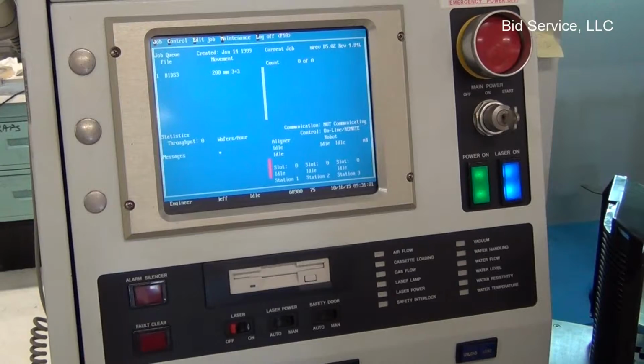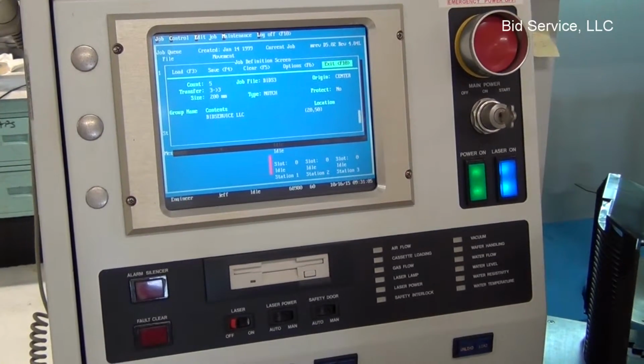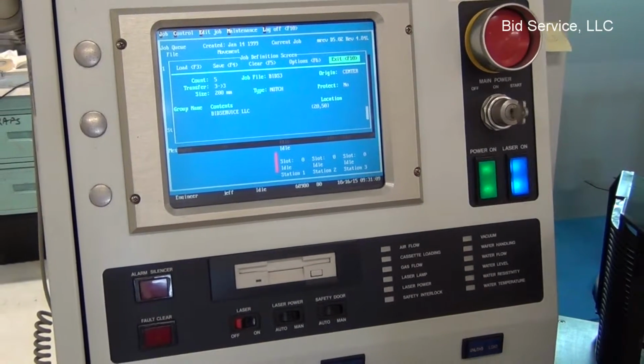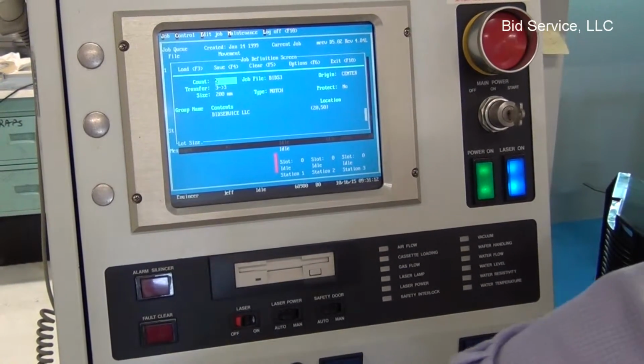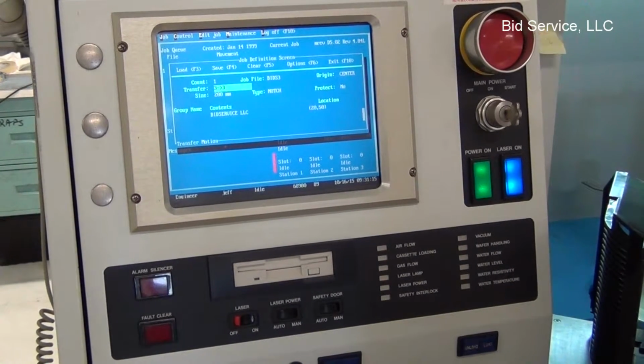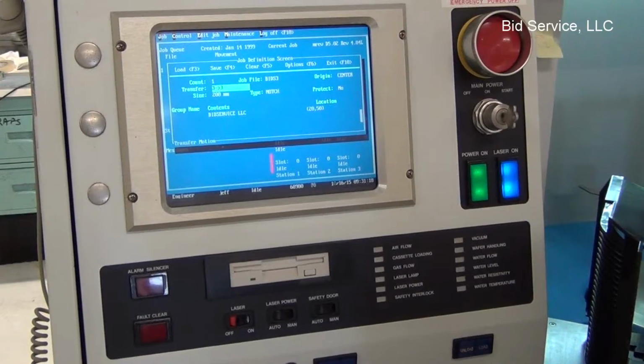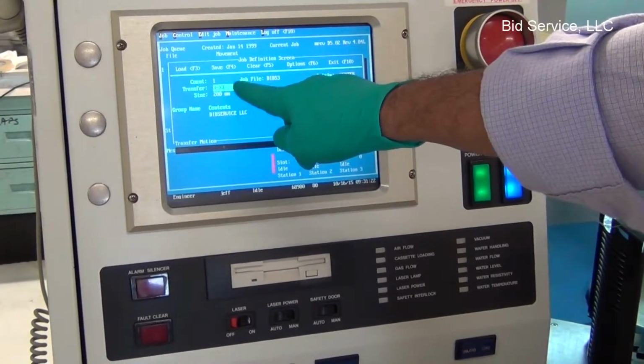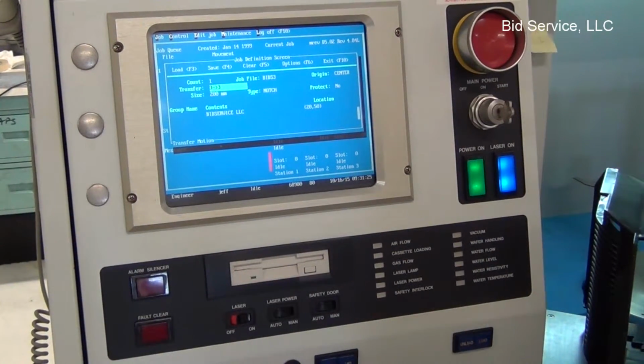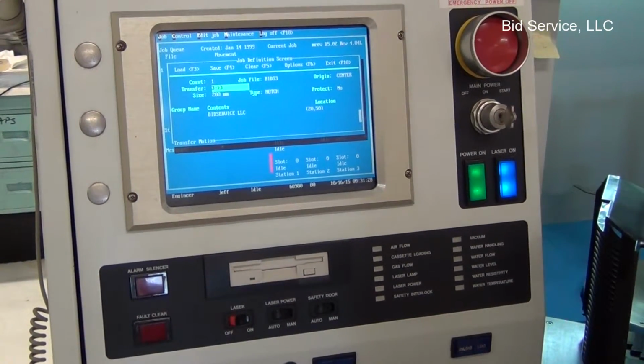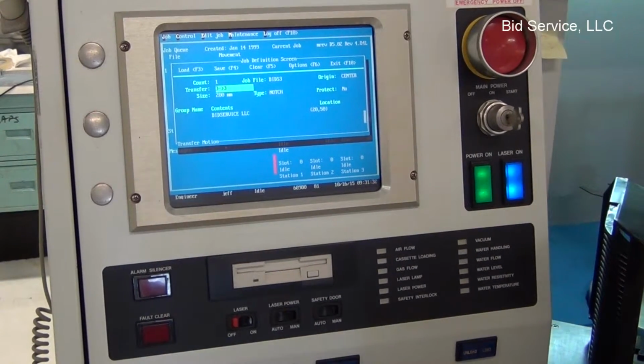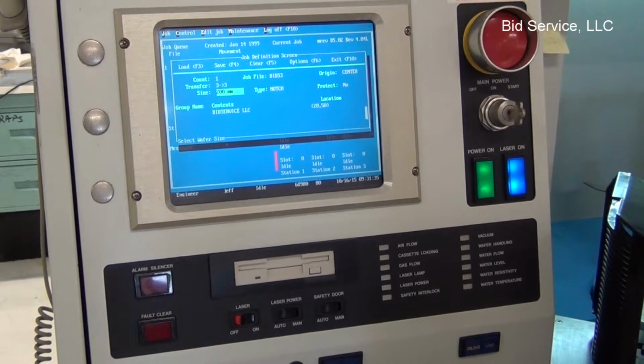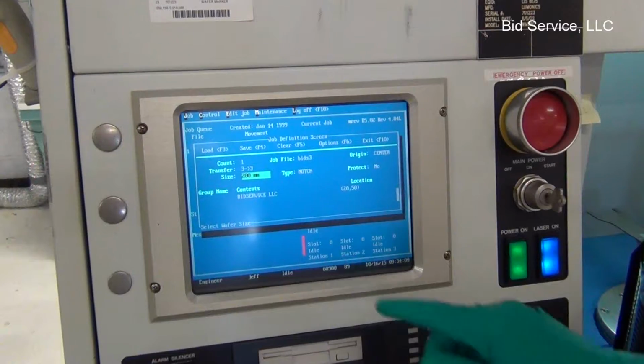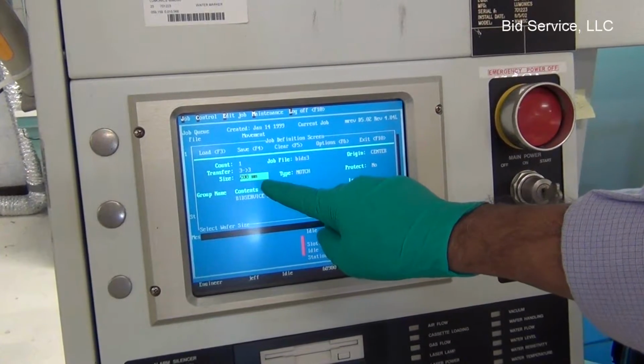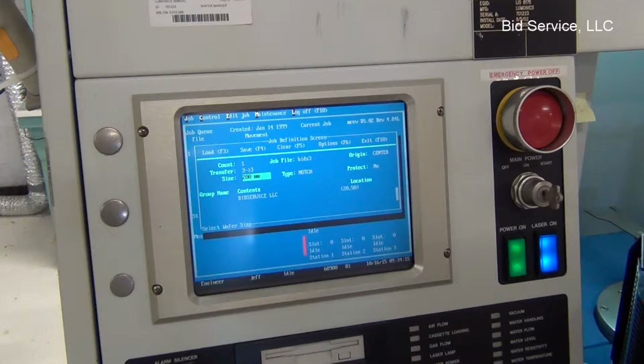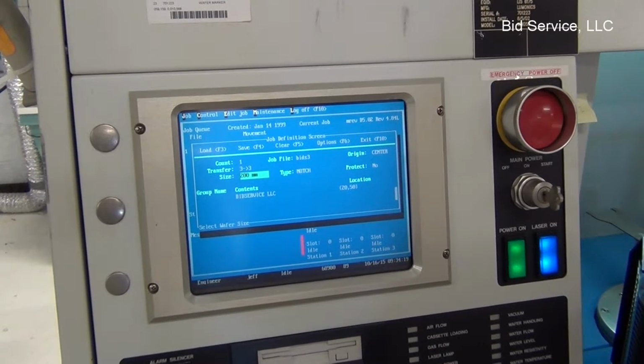To edit any job, we will go to the edit job screen, and here I'm going to demonstrate how to edit. The count is for the number of wafers, and the transfer could be 1 to 1 or 2 to 2, which represents the transfer from and to station. So currently station 3 is selected, which is the extreme one on the right. The size of the wafer is 200 millimeter, that's what I'm running. The size is currently selected for 8-inch or 200 millimeter. This can be changed to a minimum of 100 millimeters or 4 inches.